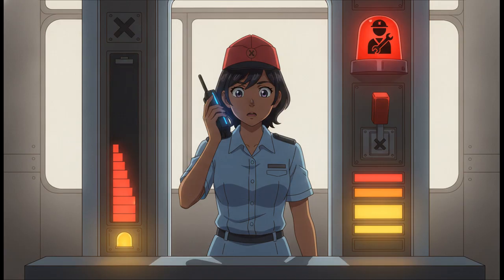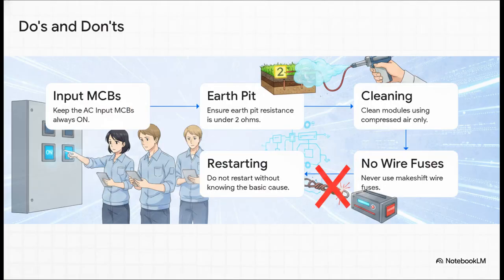If the battery discharges to 50%, an audio alarm sounds and the start generator light glows. Drops to 60%, the warning intensifies, prompting an emergency start. If it reaches a critical 70% discharge, hitting exactly 105 volts, a forced system shutdown kicks in to prevent the battery from dying completely. And what if an individual module fails? A bright red Call S&T staff light immediately tells the station master it's time to call in the signal and telecommunication engineers right away. Now, when the engineers actually arrive, the stakes are incredibly high.